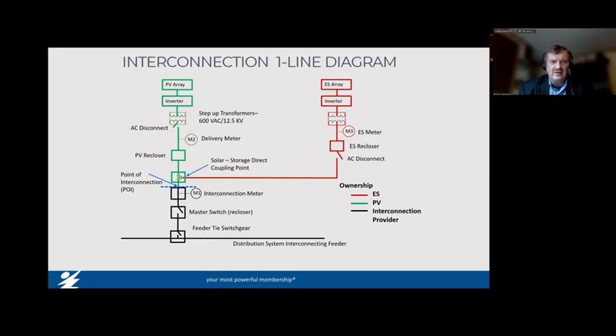And then from there, we have cables that steps into what we call the interconnection meter. Now that is a meter, but we use that more for operational monitoring and energy archiving than anything else. We don't use it for billing. It is basically a point of operational information. And then we go through a master switch. Again, that's a big pad mounted circuit breaker on the ground. And that Connexus owns and has control of to trip and close to either take the site offline, the entire site, or put it back in service.